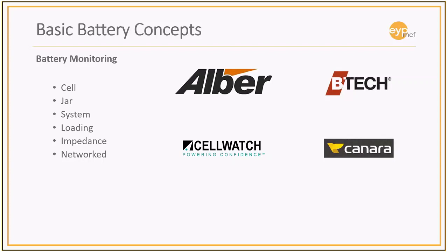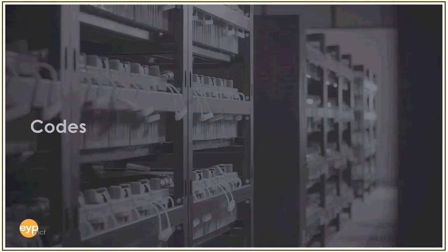Even if you're not doing a discharge, you look at it on a regular interval to make sure that you're not having issues with your batteries, because you really never know that you're going to have a battery problem until you go to do the discharge on those batteries, and then it's too late. So it is really important to monitor the health of those batteries.